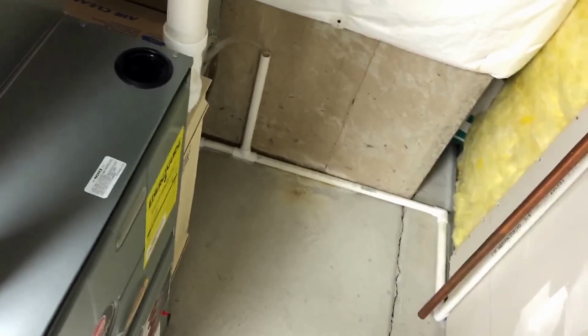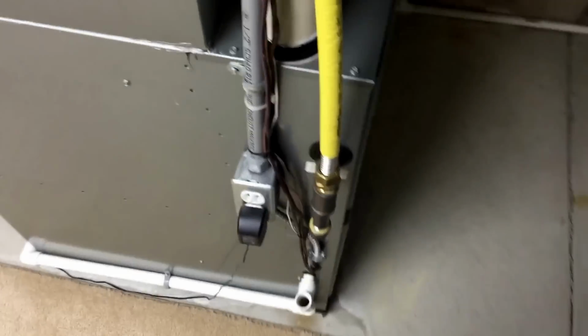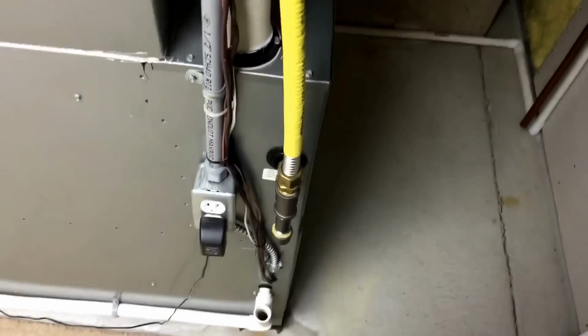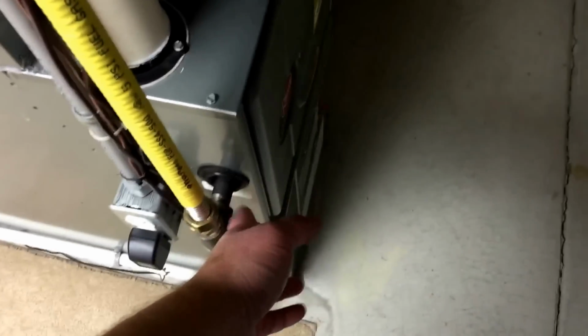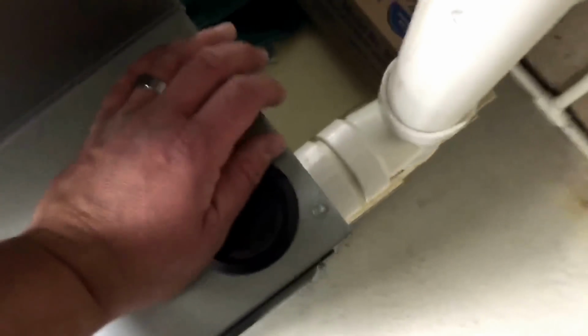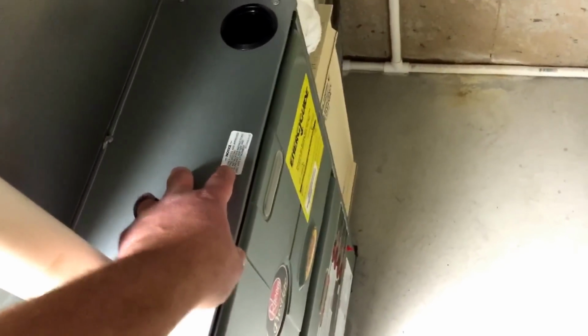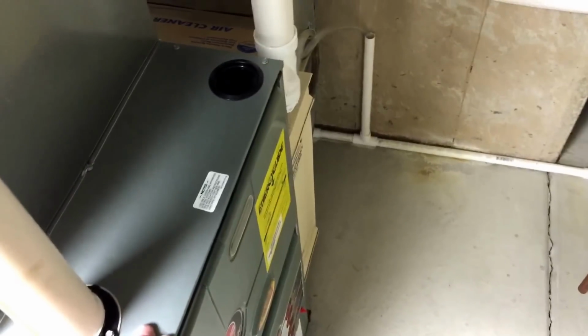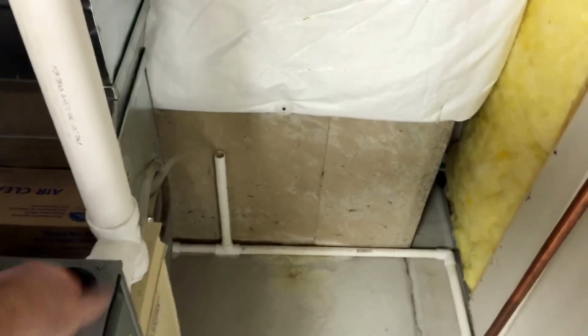They actually had drilled a hole instead of using the proper hole with the proper grommet and everything to run a gas line into the furnace. They drilled a hole in the side of the furnace to run the gas line, where every manufacturer that makes a furnace provides proper holes to run the gas line in. There was no need to drill a hole. Also, all these grommets were missing on the furnace. Like I have one here. This is a Rheem furnace. So all these grommets and gaskets are required so that this furnace runs efficiently and correctly. This is a sealed combustion furnace, which is also the same as the one I looked at yesterday. And, you know, no outside air piped in, just drawing air from the basement.